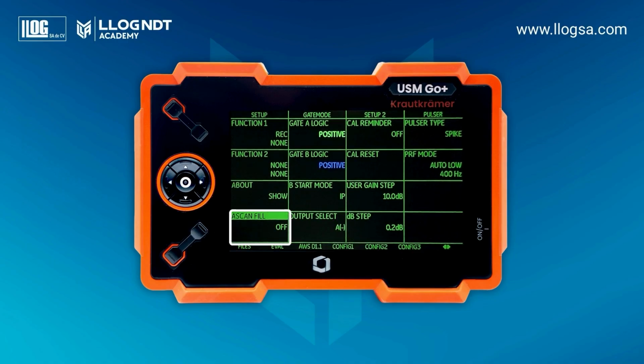Fill echoes on the A-scan. Enable or disable gates A and B. Automatic tracking of gate B in relation to gate A. Visual alarm output for both gates. Calibration reminder at a defined interval. Reset calibration reminder. Set gain step as predefined or custom. Select pulse type, either spike or square. And finally, adjust the pulse repetition frequency.